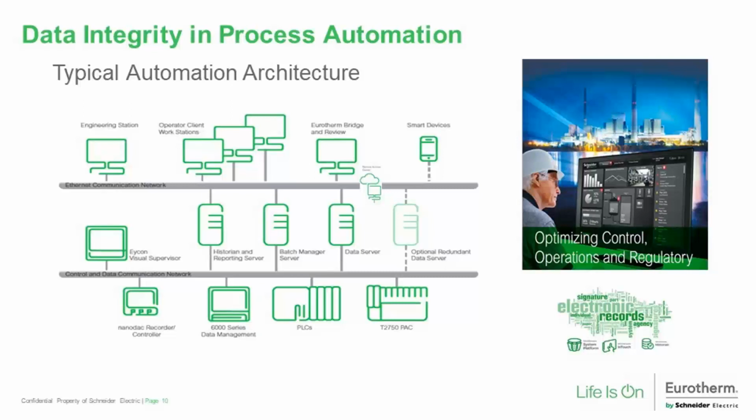The middle layer starts to get up into the system, if you will, where you have a box such as this one here that's your primary data collector. He's the one that's got all the real-time data. And sometimes that one's so important that it's often made redundant, and there's another one sitting off to the side doing the exact same job in case the other one fails.